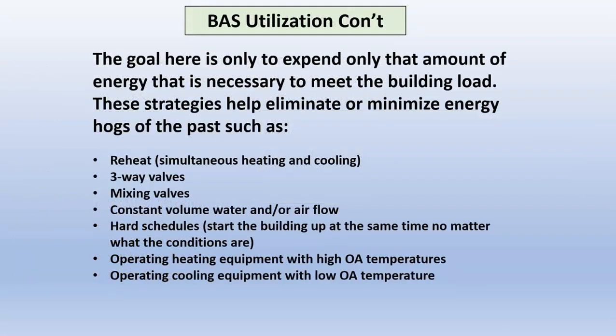All right, more utilization. The goal here is to only expend that amount of energy that's necessary to meet the building load. So here's a few strategies that you can get, and some equipment that you can eliminate by using your BAS. Reheat, simultaneous heating and cooling. The new energy code forbids it in most cases, but back in the day, 4-pipe system, you pretty much put it together to run both of them at the same time all the time. Terribly inefficient. You would never build a system like that today using the new energy code. But using your BAS, you can minimize reheat or eliminate it.